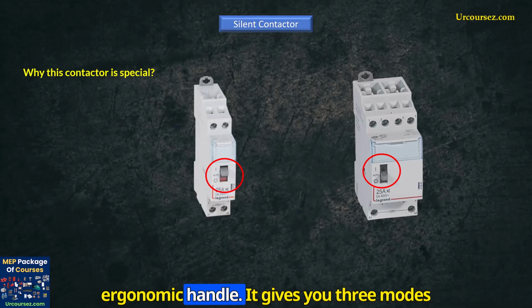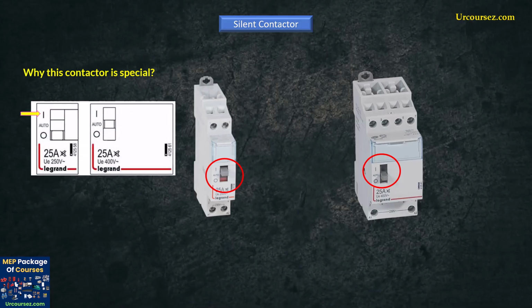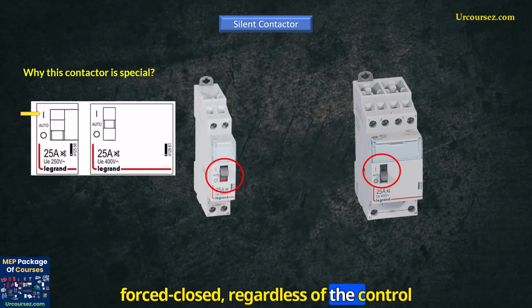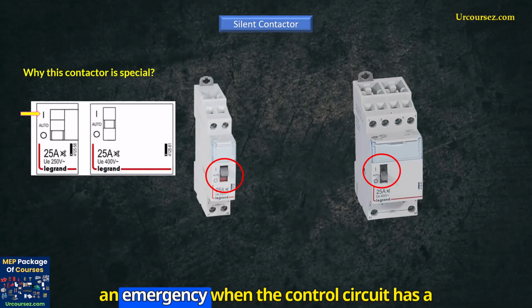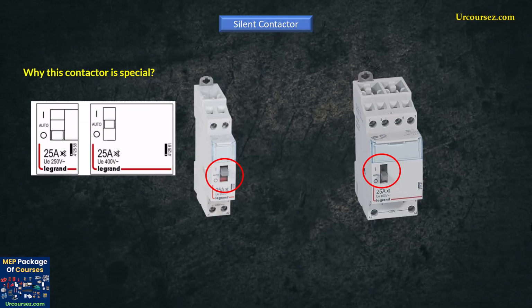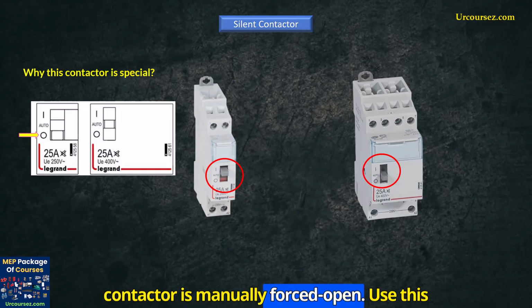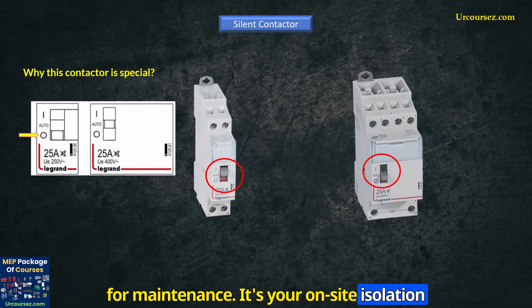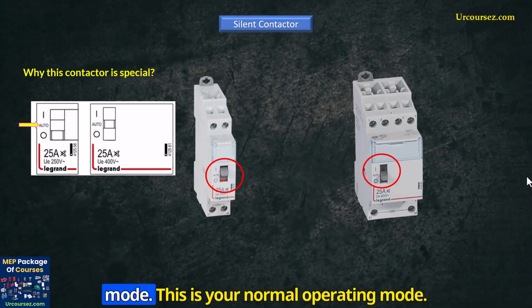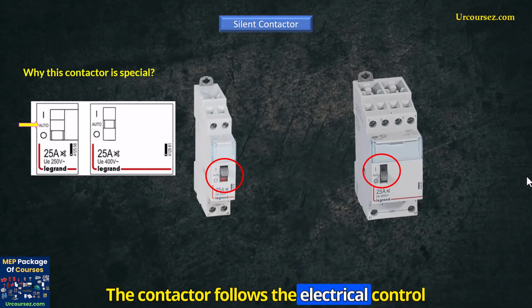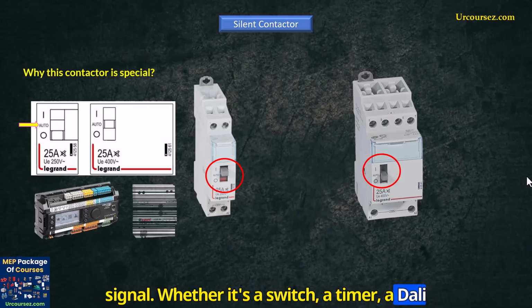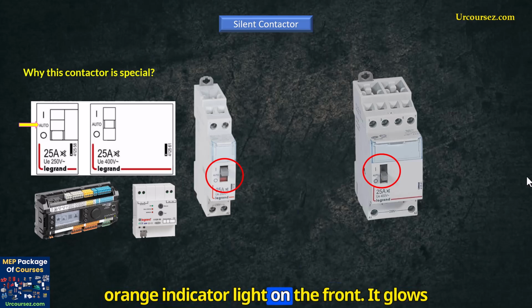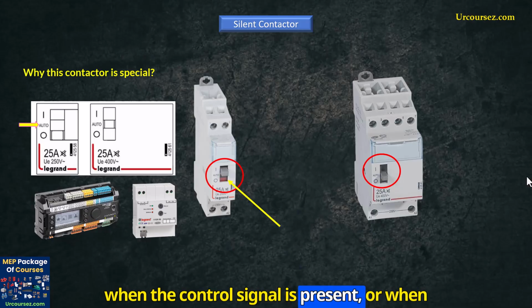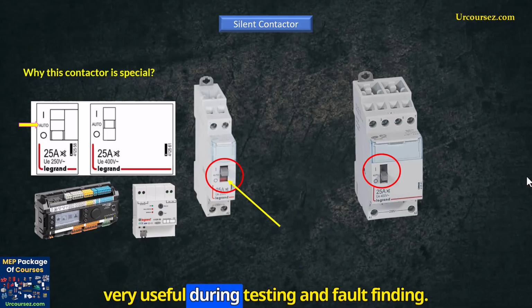Now here's a feature that makes this contactor special on-site: the 3-position ergonomic handle. It gives you 3 modes of operation. Position 1, forced on. In this position, the contactor is manually forced closed regardless of the control signal. Use this during commissioning or in an emergency when the control circuit has a fault and you need the lights on. Position O, or forced off, where the contactor is manually forced open. Use this for maintenance. It's your on-site isolation for that circuit. Position auto, or automatic mode. This is your normal operating mode. The contactor follows the electrical control signal, whether it's a switch, a timer, a DALI gateway, or a BMS output. And there's an orange indicator light on the front. It glows when the control signal is present or when the contactor is in forced on mode. This is very useful during testing and fault finding.